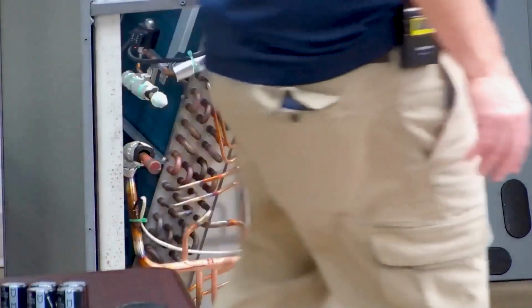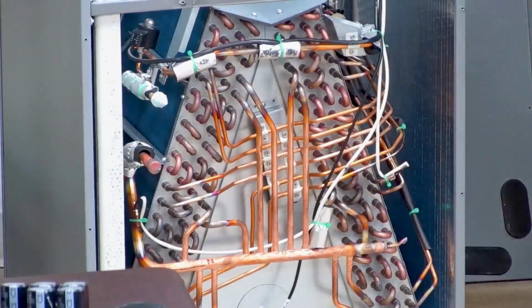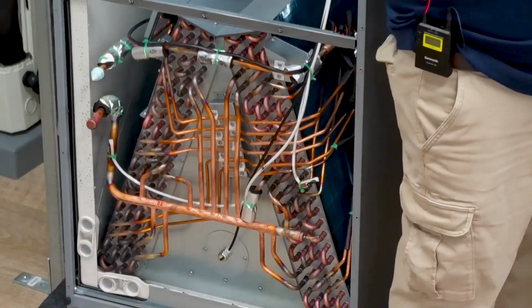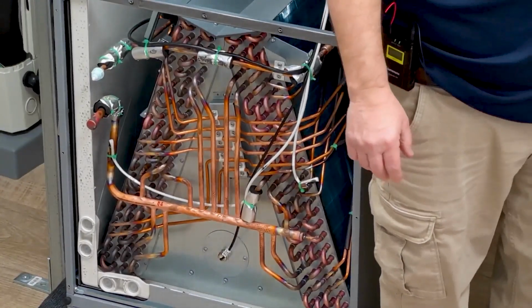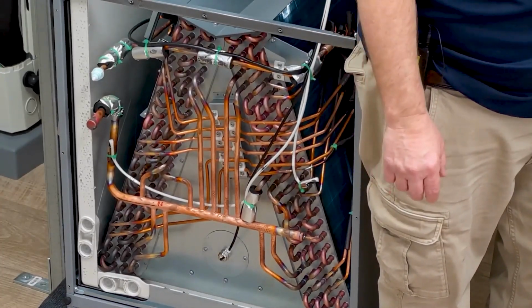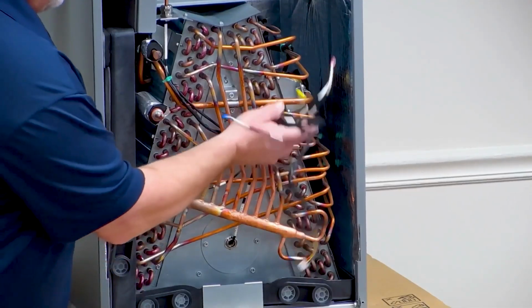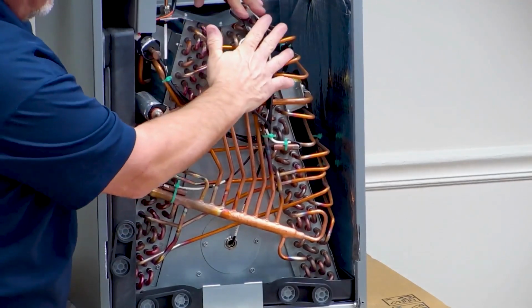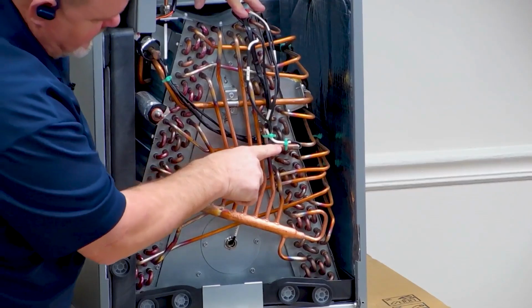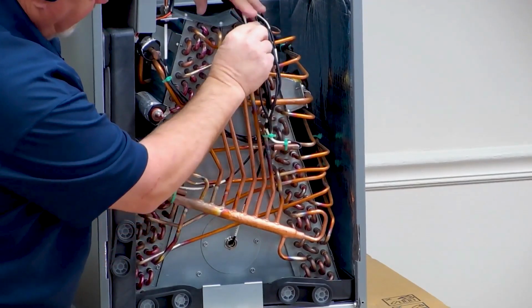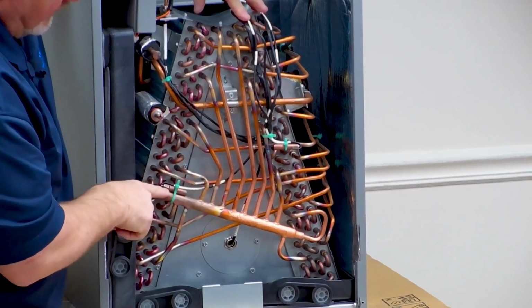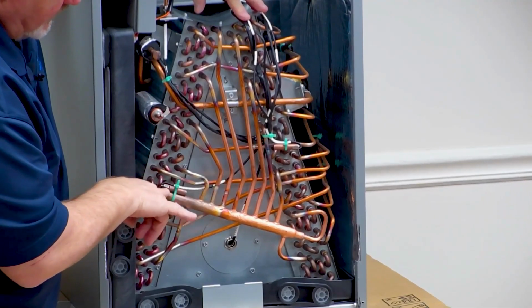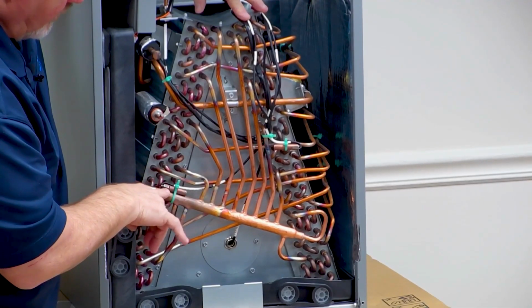So I don't have to be bent over anymore, I'm going to come over to this other coil that's doing the same thing. This is our new dual fuel coil. Make sure Nick's following along with me here. I've got the whole control panel taken off just for show and tell. Here's our inlet pipe temperature sensor, and here's my outlet pipe temperature sensor. They're a lot easier, a lot closer together on this particular coil.